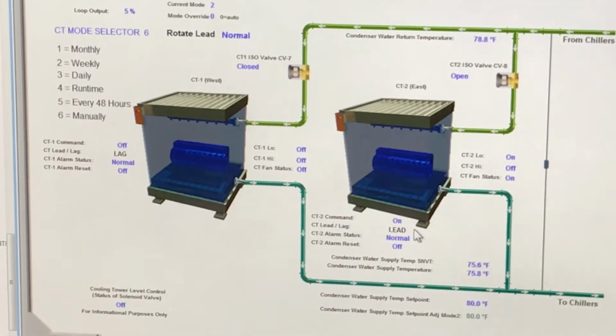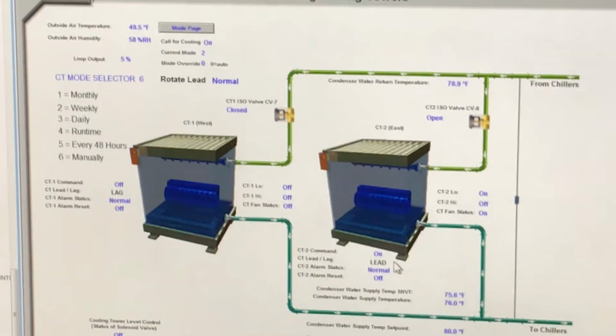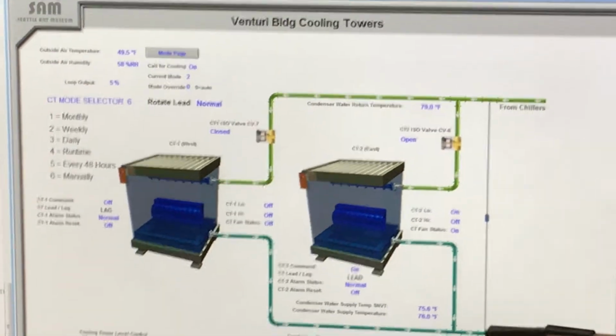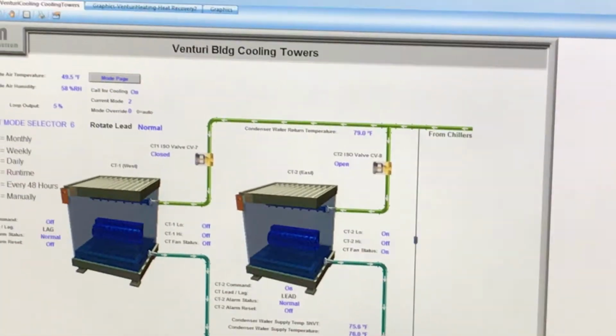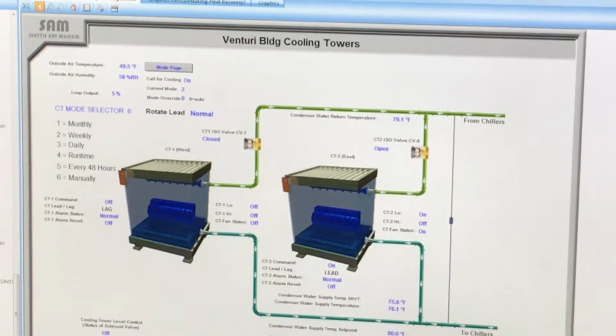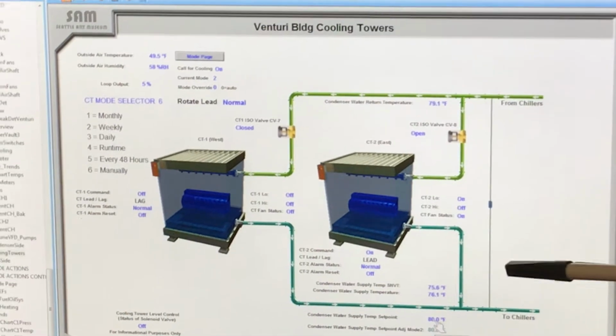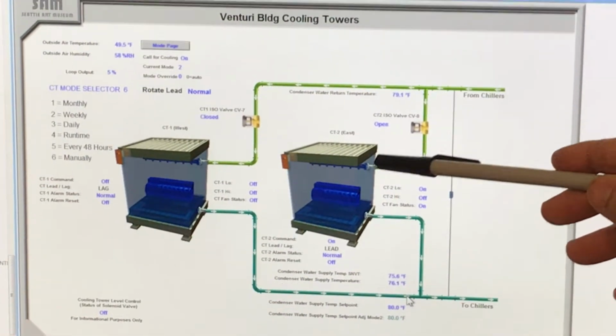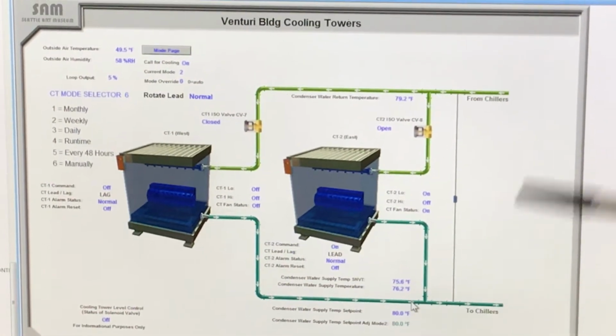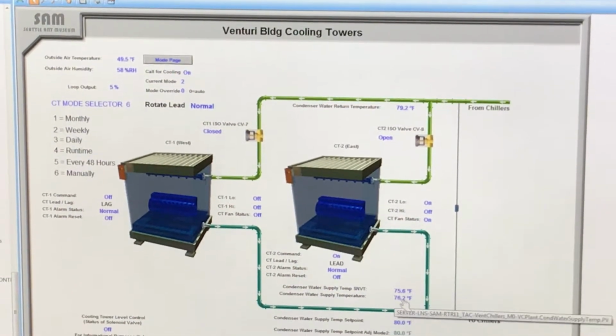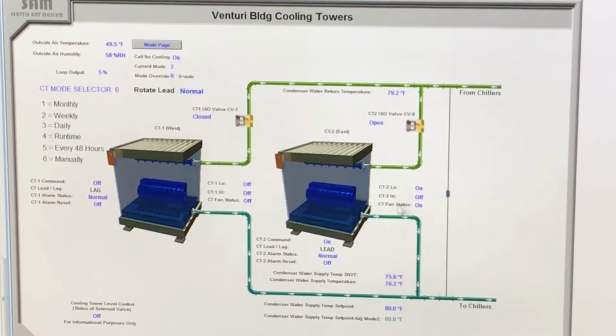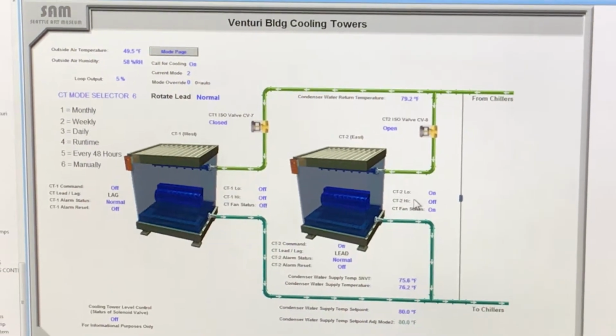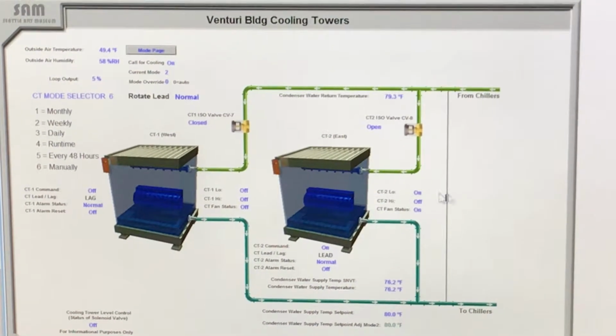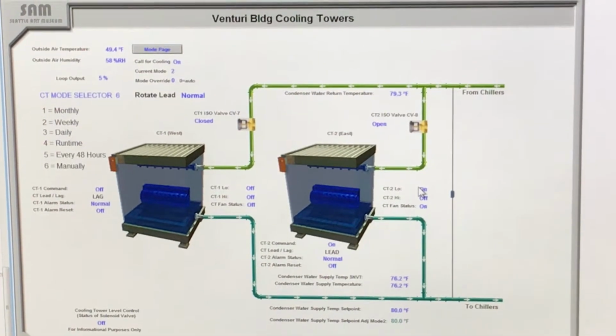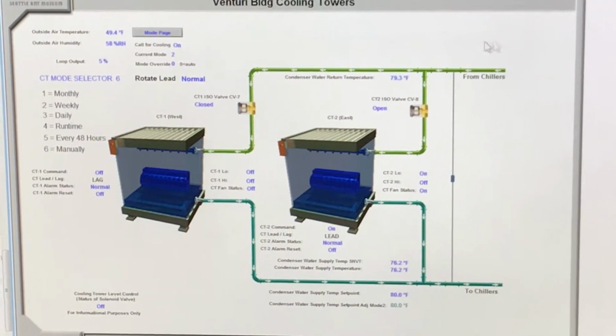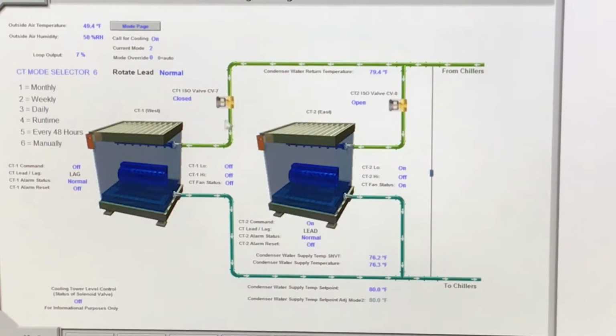So set point means the temperature coming out after the heat dissipates? Yes, the leaving water temperature from the tower, which is 80 degrees. Hot water comes in and is dissipated, then leaves. Right now it's 76, so below set point. We only have one running, and it's on low now, so it'll probably stay there. Coming in is 79 degrees, so it's not a lot.